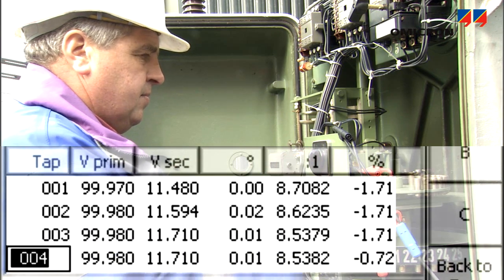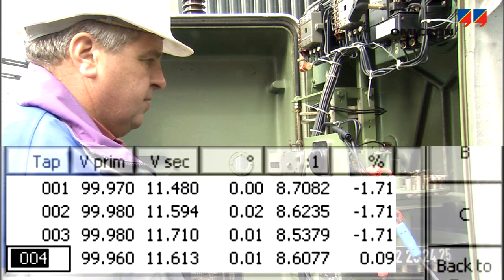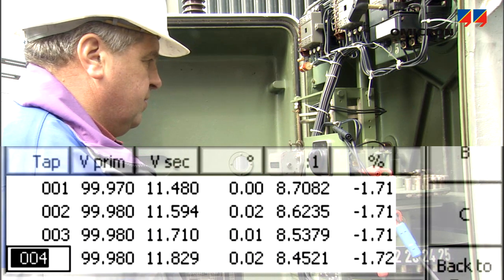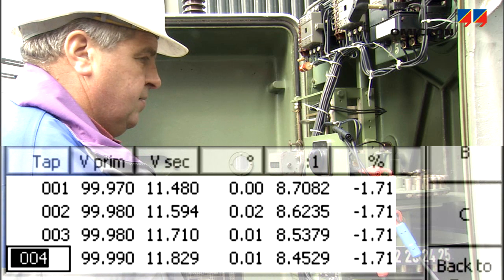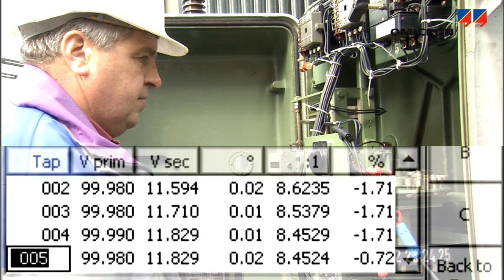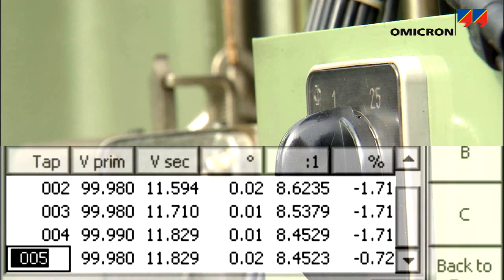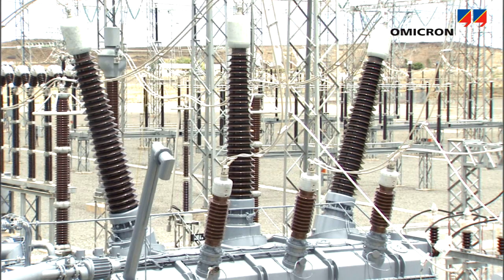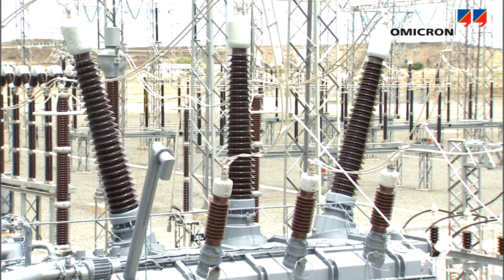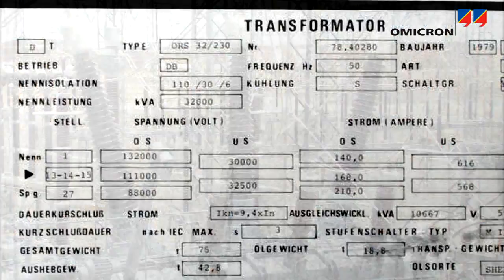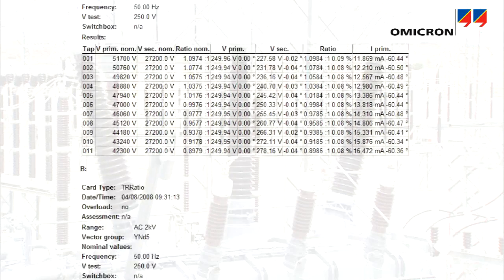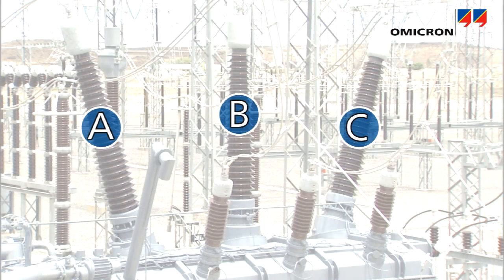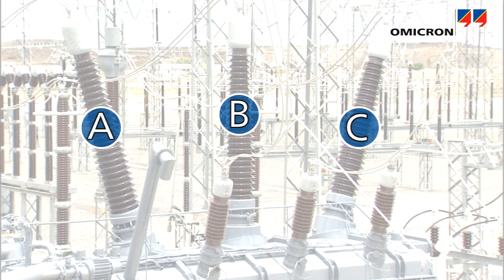The CPC measures and displays ratio, signal phase angle, and the deviation from the nominal ratio in percent. The transformer's condition is evaluated by comparing these results to specifications, factory testing results, or across transformer phases.